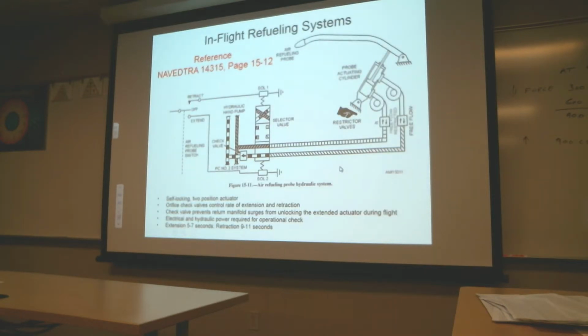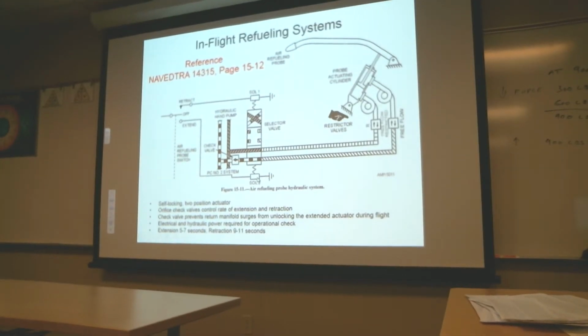In-flight refueling systems on military aircraft let them extend a probe for air refueling, using a solenoid selector. This is an ISO schematic of a solenoid selector with two main switch positions, off, retract, and extend. Putting the switch to extend routes hydraulic fluid into the actuator, with return flow through one of the solenoid selector connections. Retract is a momentary switch that applies pressure to the other side of the actuator, recovering fluid on the opposite side.